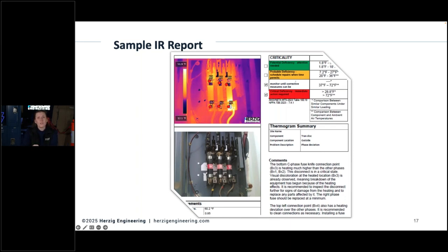Well, it could be a loose connection. Eventually that could fall out of its connection, out of its lug or termination, and cross phases. It could hit the side of the disconnect and just randomly blow up on you, causing an arc flash. If it's a loose connection, that can absolutely happen. It could overheat to the point where it starts an electrical fire, depending on how and where it's installed. So having these infrared reports is a proactive way to identify and prevent electrical hazards.